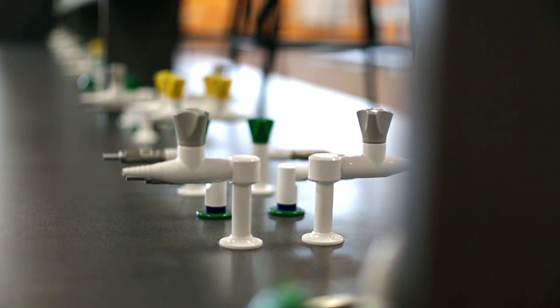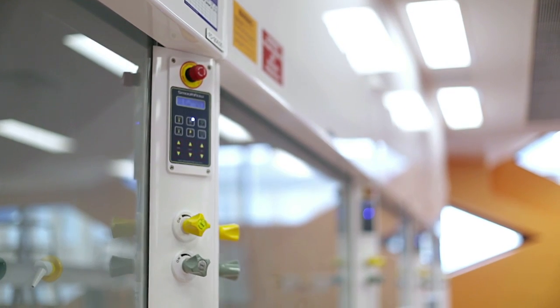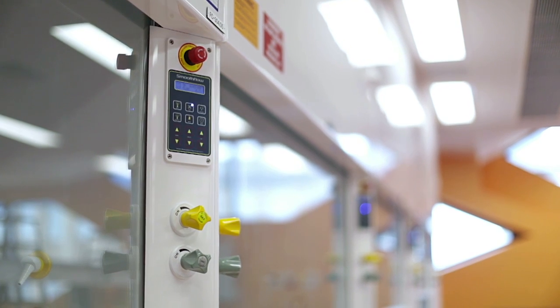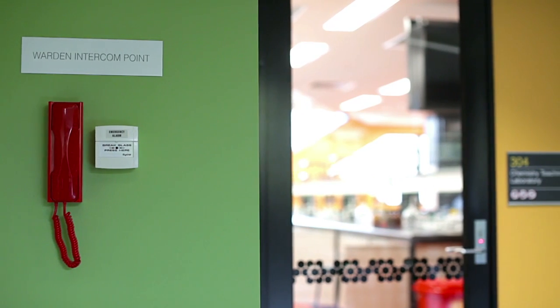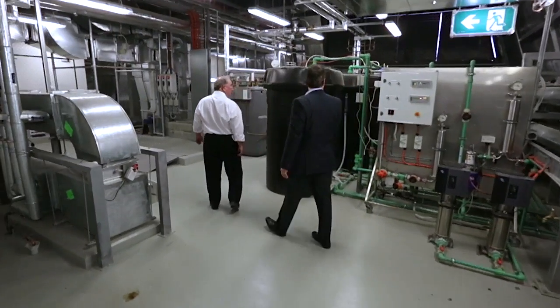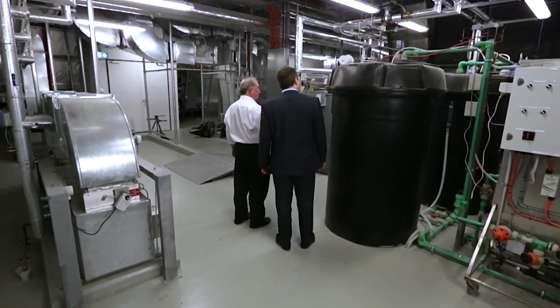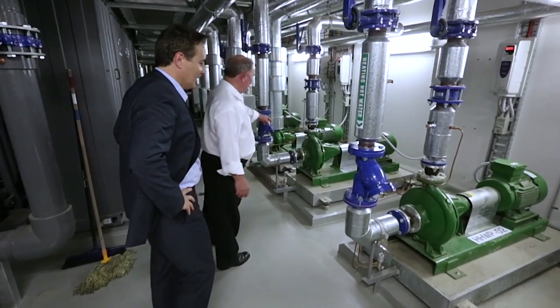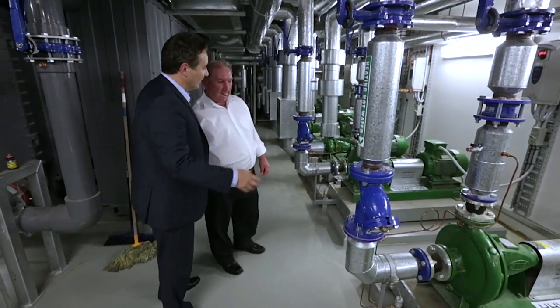In terms of the scientific areas of the building, which were more challenging, we have put in a closed system process cooling loop. So rather than discharge wastewater used for process cooling to external wastewater systems, we actually harvest that separately. We run that through a loop which is collected in a settling tank.